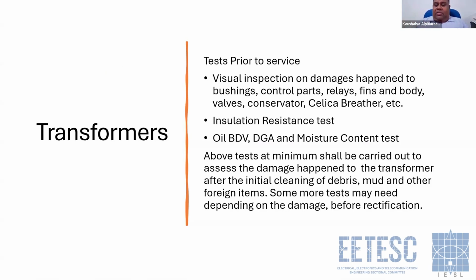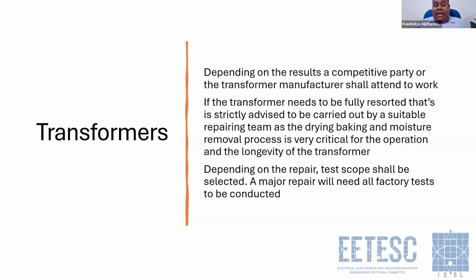Cleaning those debris and all can be done, and depending on the test results, you have to select a competent party if we are going to rehabilitate or recondition this. If you remember in the list that NEMA gave, they have specifically mentioned that depending on the oil test results, you can decide whether you are going to retain this transformer or you are going to replace it.